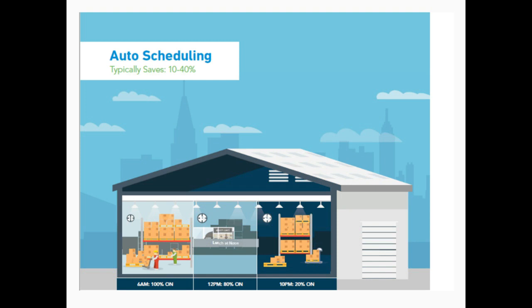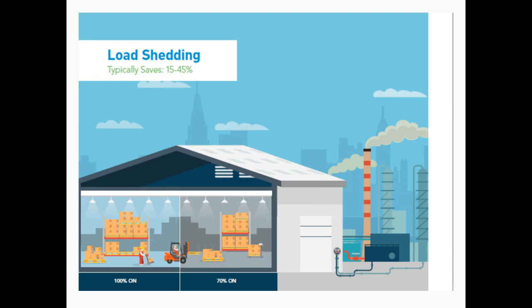The best part of the scheduling strategy is the subtle little things that can be tried and managed that save 2% here or 3% there. These savings stack up, with the broader range being between 10 and 40%. What's a smart way to reduce peak pricing or comply quickly with a utility's demand response request? The load shedding strategy reduces energy usage temporarily, either automatically based on a demand response signal or manually.